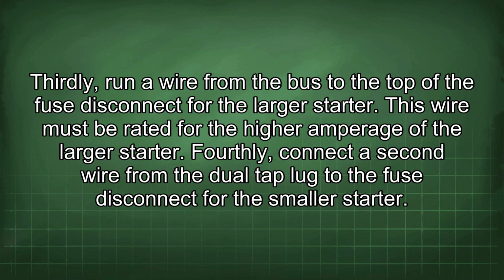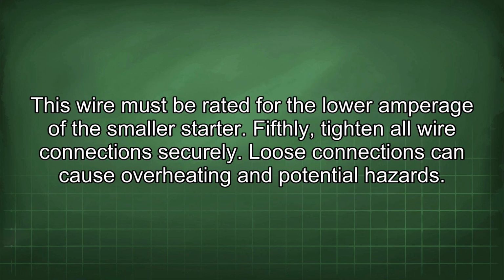Thirdly, run a wire from the bus to the top of the fuse disconnect for the larger starter. This wire must be rated for the higher amperage of the larger starter. Fourthly, connect a second wire from the dual tap lug to the fuse disconnect for the smaller starter. This wire must be rated for the lower amperage of the smaller starter.